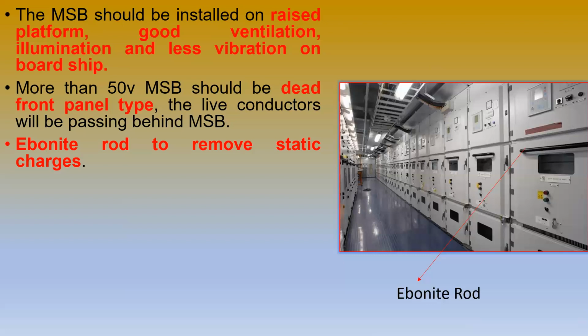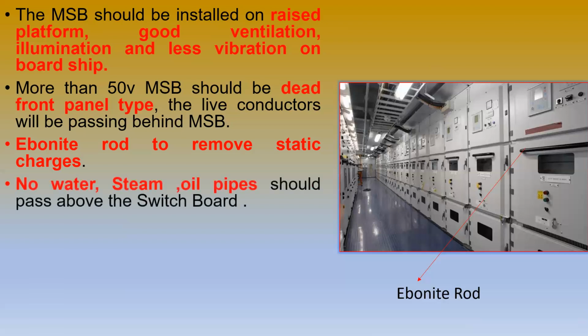So what this ebonite rod, this hard rubber, is doing is absorbing the charges. It absorbs the charge and does not discharge it. It does not dissipate it. It keeps it for itself. And that way it is protecting the human being as well as the machineries, as well as the MSB board. So this is also one of the important points for the safety of MSB. Next is no water, steam or oil pipe should pass above the switchboard, or any conducting material. This type of thing should not pass near the vicinity of the switchboard. It should be properly installed where proper ventilation and proper lighting are available, and there should not be any pipelining.